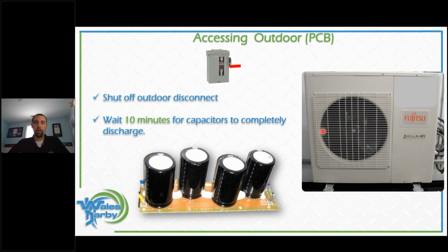I always like to take a multimeter, especially in my territory. I'm in a city. There's no way in hell I'm going to hear that thing click. But if I put a multimeter on my incoming power, I'm going to watch that power drain. Sometimes it's less than 10 minutes, but you don't want to take a chance. I always wait at least 10 minutes just to be sure.